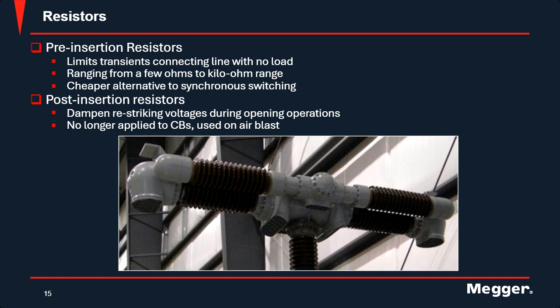with no load. They are only used during closing and are connected in parallel with the main contact. The pre-resistor connection closes about 8 to 12 milliseconds before the main contact, and the resistor provides that inrush limiting by the momentary insertion of the resistive device into the circuit before fully energizing.